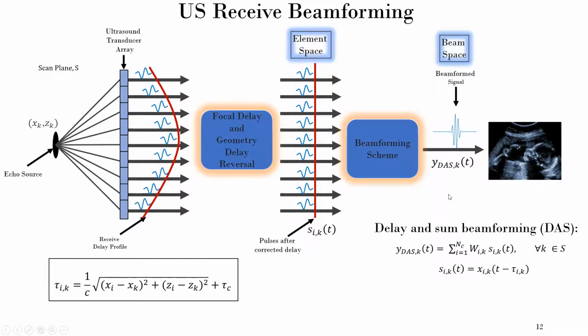Of course, I'm skipping a lot of small processes in between because this is a very generic lecture. I don't want to go into all the details, but this is the holistic picture that I can give you. So transmit beamforming is separate, receive beamforming is separate, but fundamentally the concept is the same. Given a pixel, you identify the distance from that pixel to the transducer array, compensate for that delay, and then you add them up together. You get the signal out from that pixel, and you repeat that process for all the pixels, stitch them together, and you get the image.